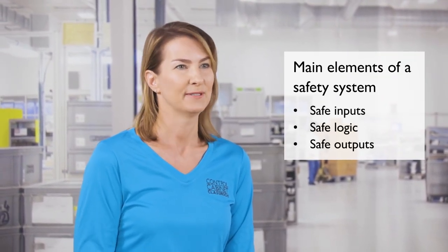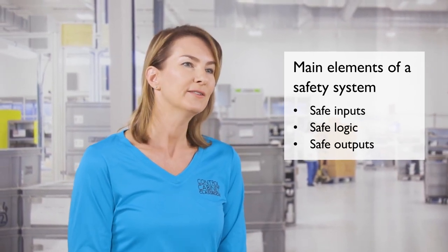That's better. Every safety system is comprised of three main elements: safe inputs, safe logic, and safe outputs. If you don't have all three of these, you either don't have a full safety function, or you're relying on non-safety rated systems to run safety logic. In most safety standards, the combination of these three elements will lead to the total risk reduction calculation necessary to determine if you've properly protected yourself against safety hazards within a system. But let's not get ahead of ourselves. In today's episode, we're only looking to show you some of the common types of safety inputs, logic, and outputs you could use in a safe application. So let's start with safety inputs.